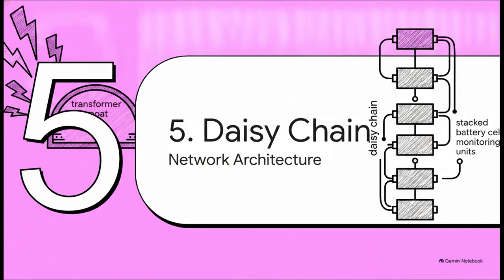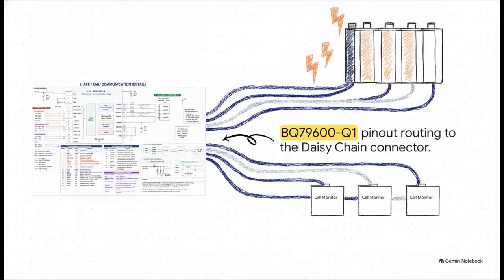Section 5, the daisy chain network. Let's trace the signal out to the battery pack itself. Notice the COM-HP and COM-HN pins on the right side of the chip block. These are your crucial differential lines. They carry the data out to the first cell monitor unit in the stack, usually over heavily shielded twisted pair cables. And that twisting naturally cancels out a massive amount of external electromagnetic interference.